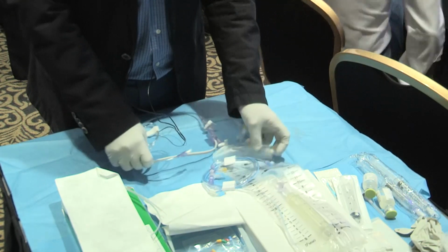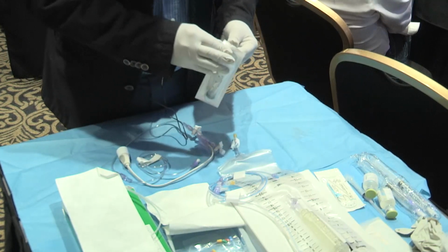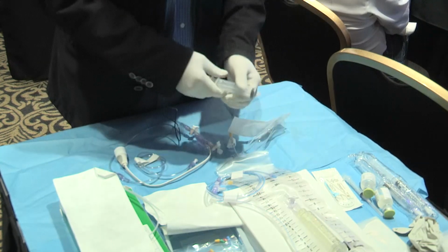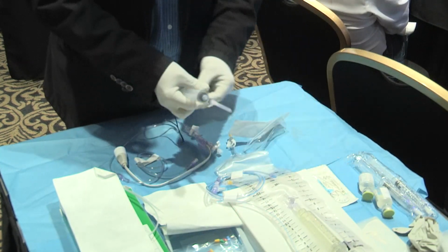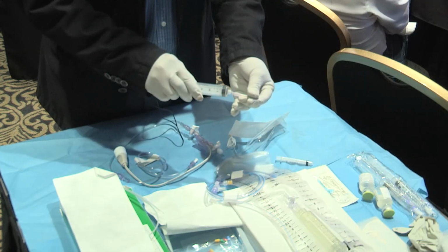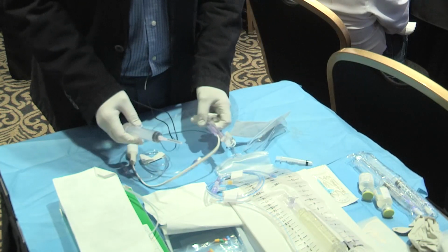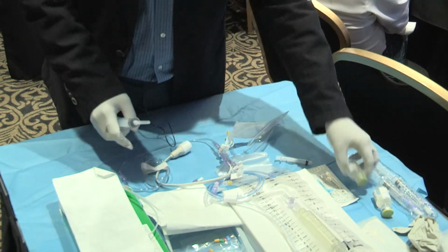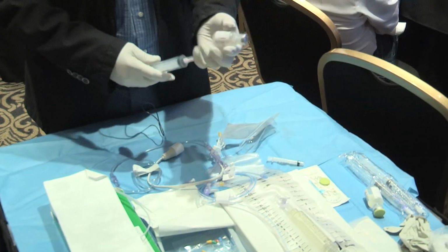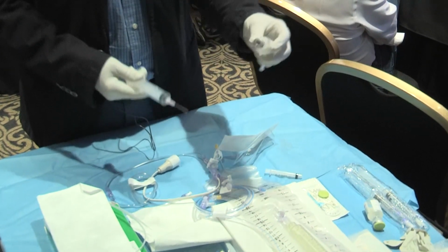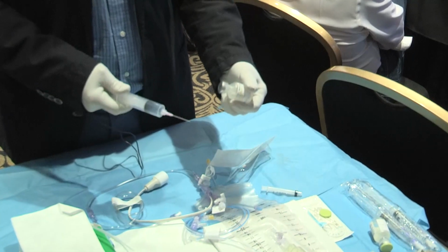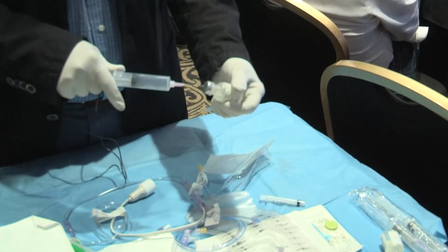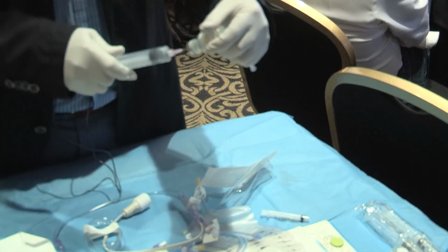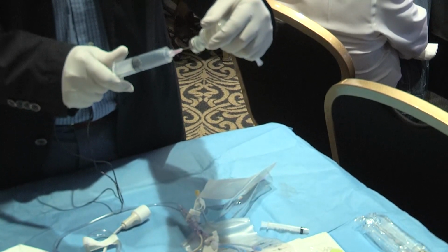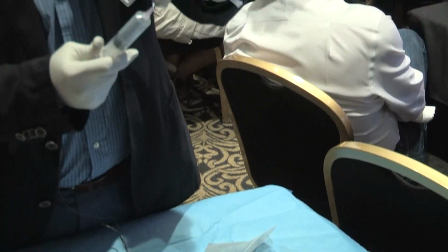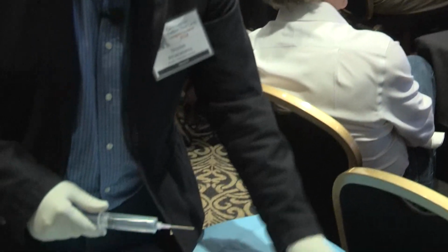It needs to be flushed, and unlike the other transducers that we set up for the invasive lines like CVP, arterial line and PA pressures, we don't use a pressurized bag for that. What we use is preservative-free normal saline. Either the anesthesia tech gives me the bottle and I draw it sterilely, or they put it in a little bowl, and again I do it sterilely. Well, for this it doesn't really need to be sterile, but the fluid has to be preservative-free, sterile normal saline.